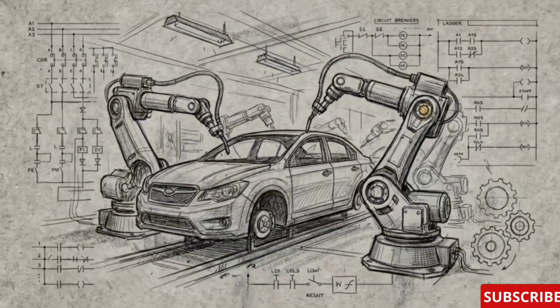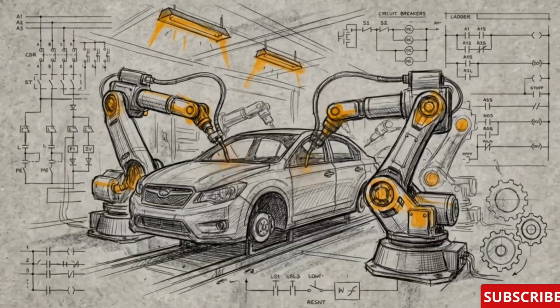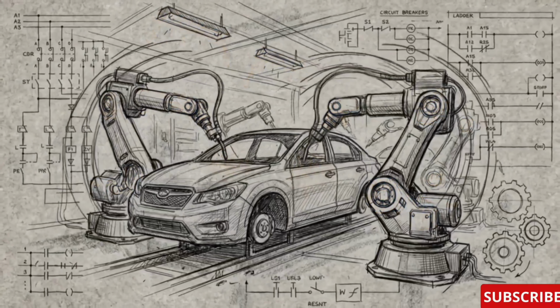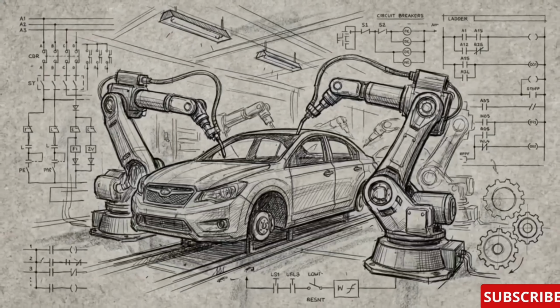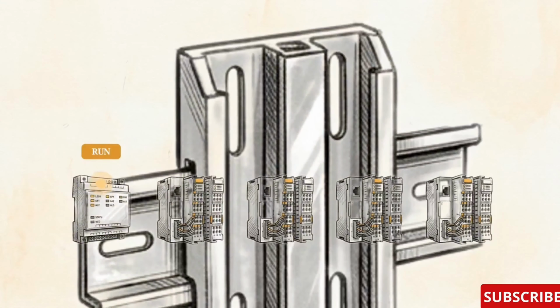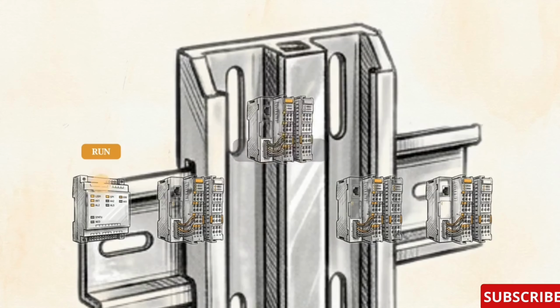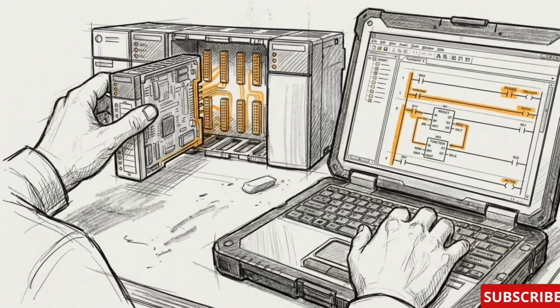The requirements change for continuous operations, where an unexpected stop easily costs thousands of dollars every single hour. For these plants, hot swapping and runtime transfers are standard requirements. These features allow a technician to replace a module or edit a rung of code while the system remains powered and the process continues to run.